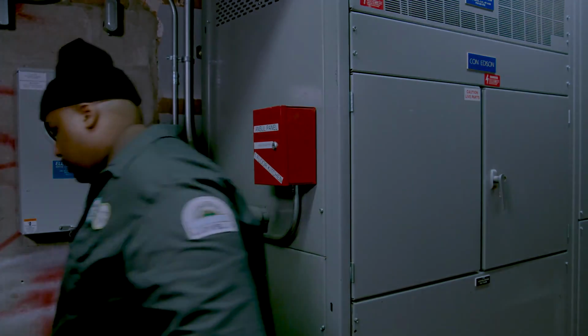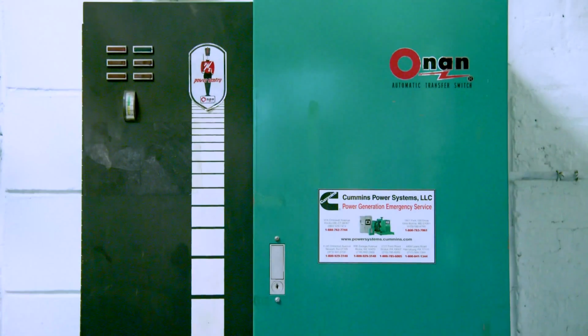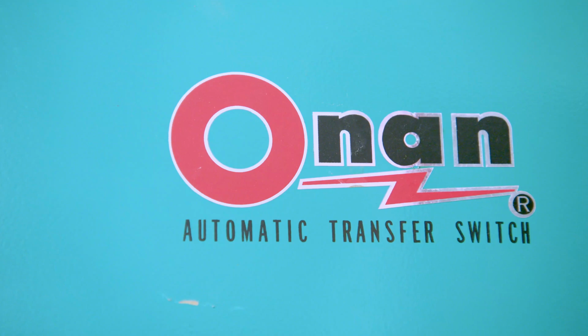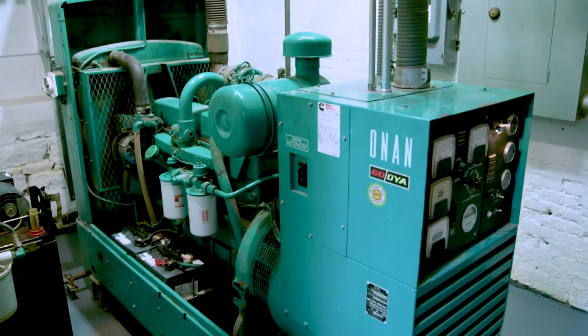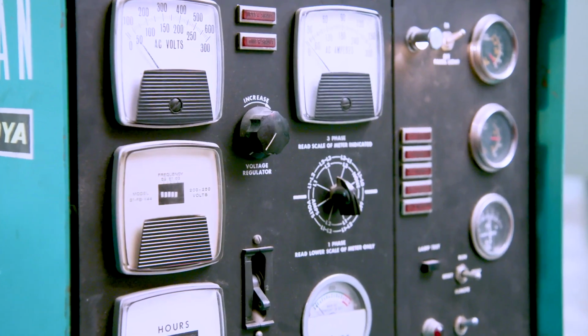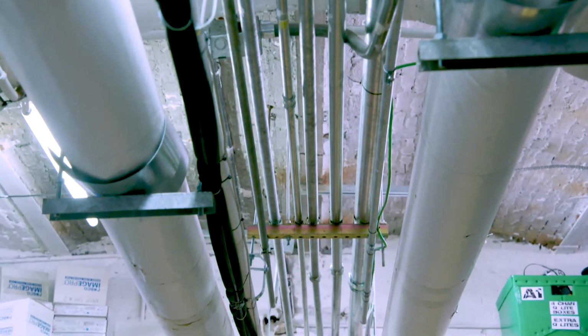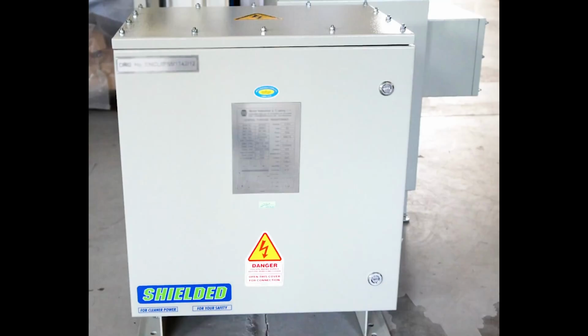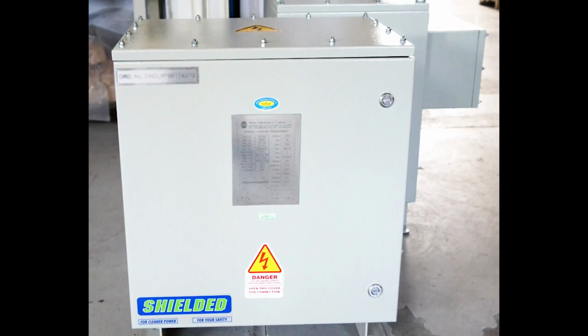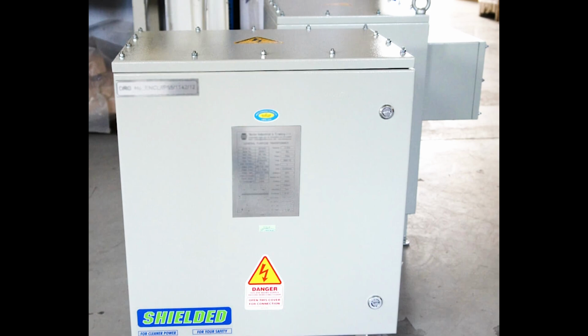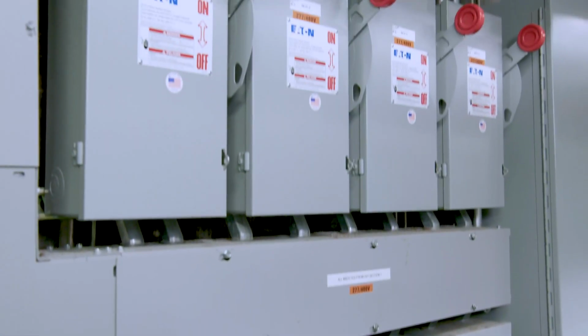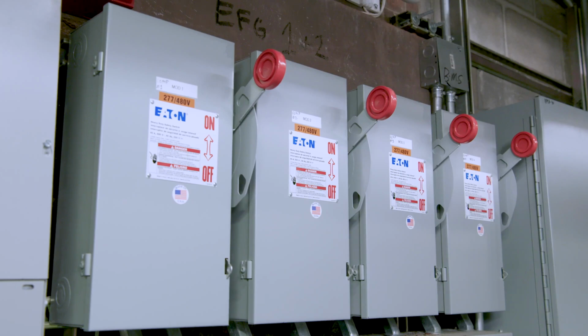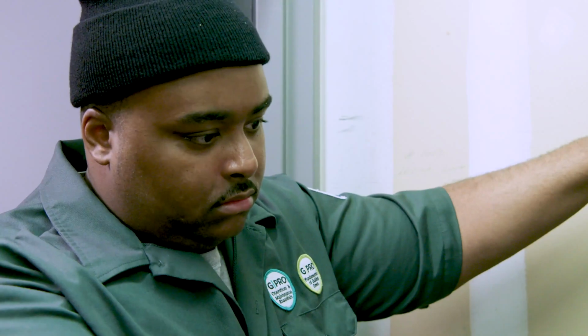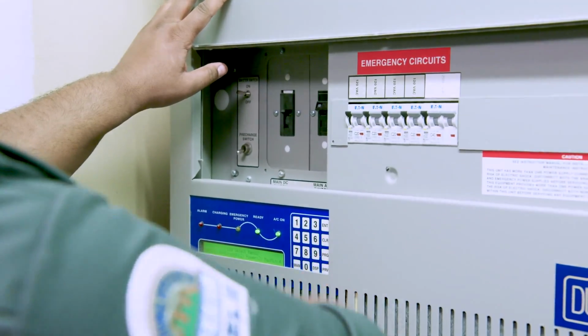Let's leave the electrical room and look at some more electrical components. If the power to the building is cut off unexpectedly for any reason, the automatic transfer switch disconnects from the grid and connects to an internal generator to provide electric power for emergency and basic systems. Wiring carries electricity to end-use loads such as motors, lighting, and other devices throughout the building. Transformers may be used to raise or lower voltage as needed for different systems or devices. Not all buildings have these. In addition to the main disconnect, there are safety switches used to disconnect specific equipment or groups of equipment for servicing. Electric lighting panels distribute power to lighting fixtures.